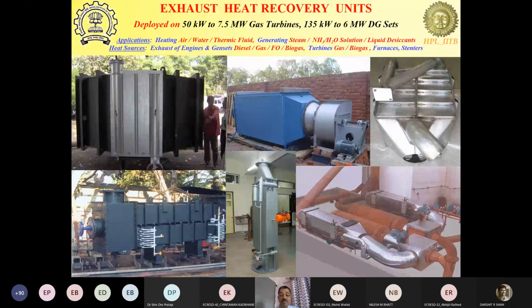Within 20 seconds of vibration, the entire dust deposited on the heat exchanger surface would drop down into the collection pan below, and the heat exchanger would be almost as clean as new. So we got a letter from the chief engineer after 3 months that they had not opened up the system for the last 3 months, and they wanted one more system like this. We gave them one more system, and then we licensed the technology to them to replicate it for the rest of their systems.